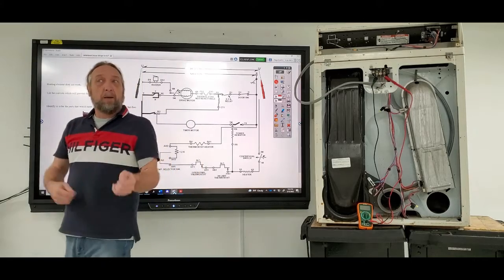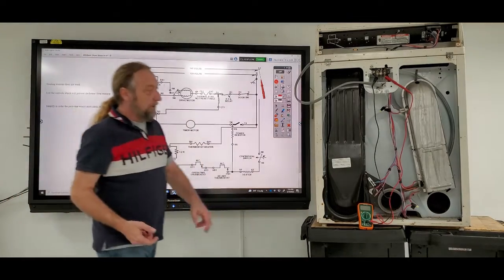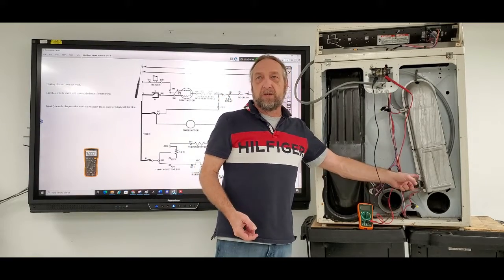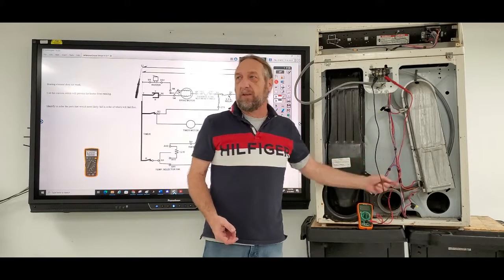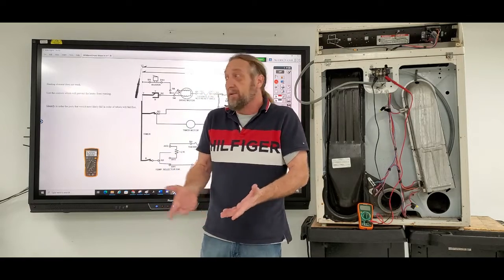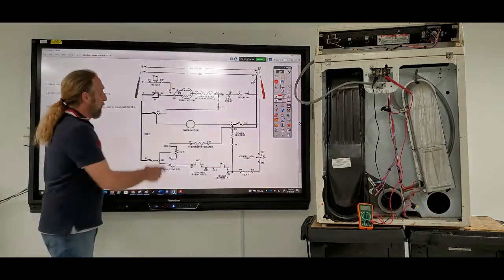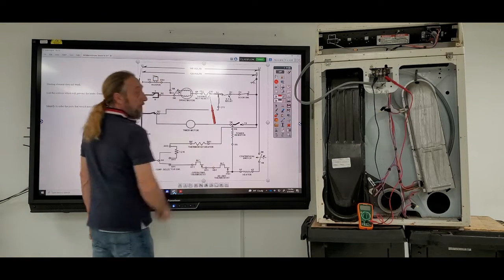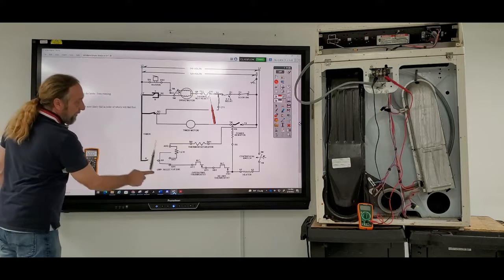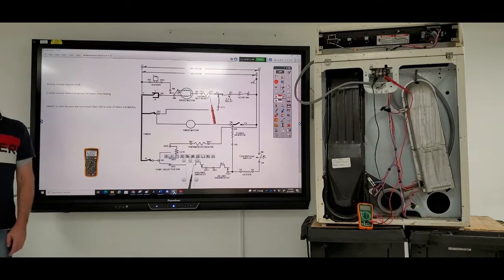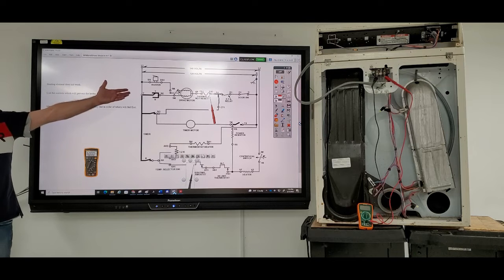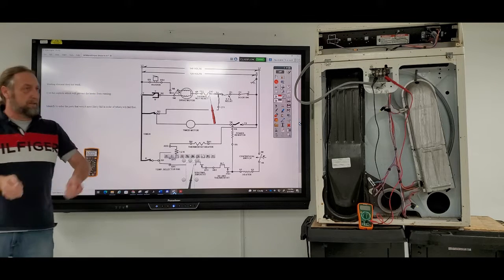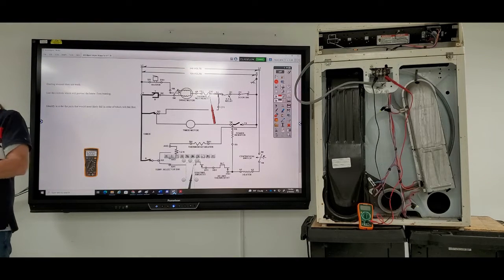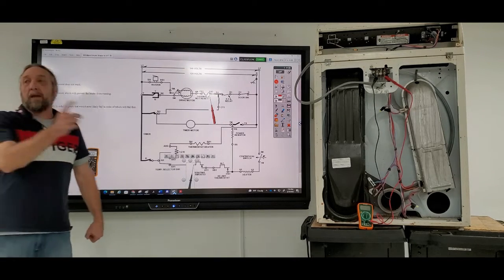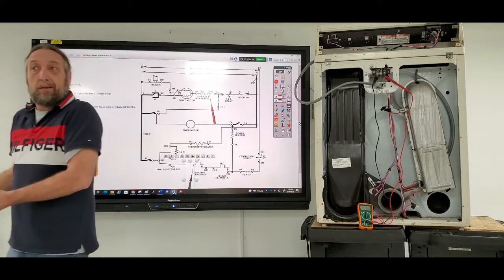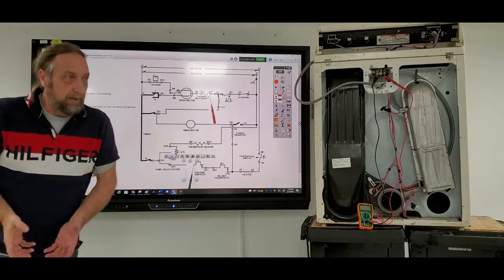Because there are technicians that make tests with one meter lead on the thermal fuse and the other meter lead on the thermostat. Well, the thermal fuse controls the motor, and the thermostat controls the heater. If he's got one lead there and one there, he's definitely not making an accurate test. What does that thermostat have to do with the motor circuit? It doesn't. So the guy's making tests, he's trying, but he's got 2 minutes left, and he just says, okay, the motor's bad. Well, he got it right, but I know he didn't actually test it. He's guessing.